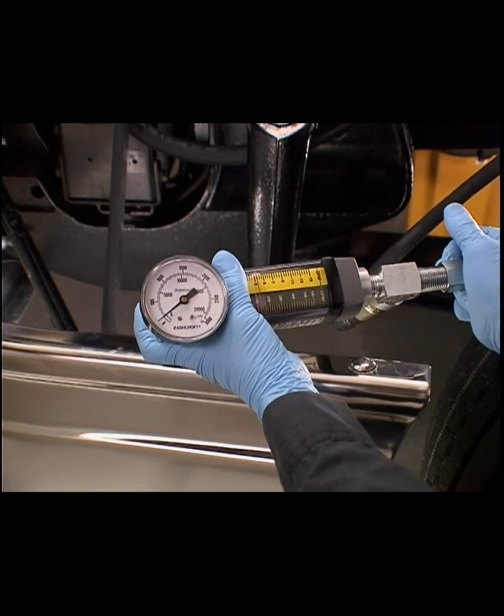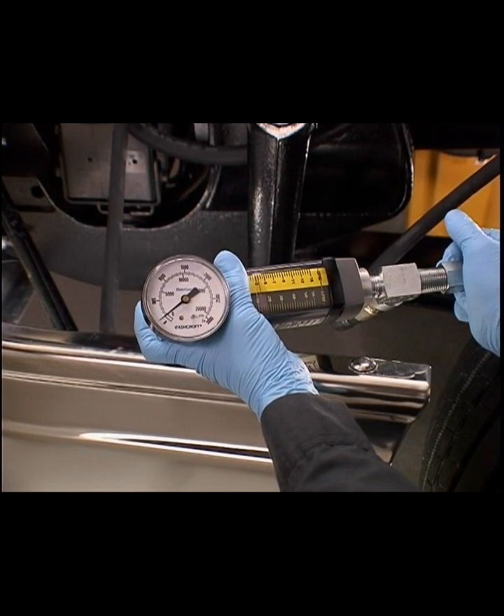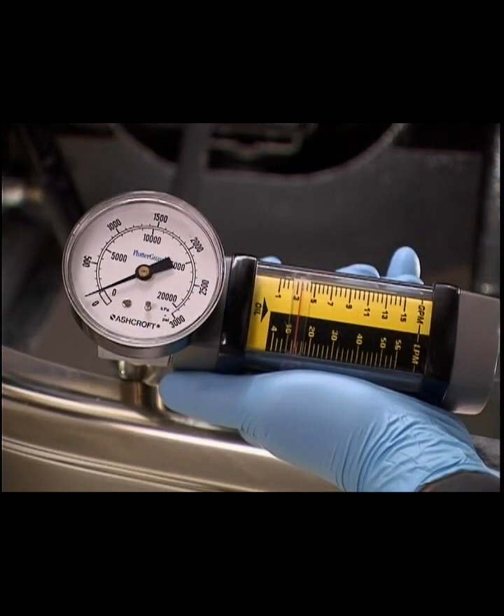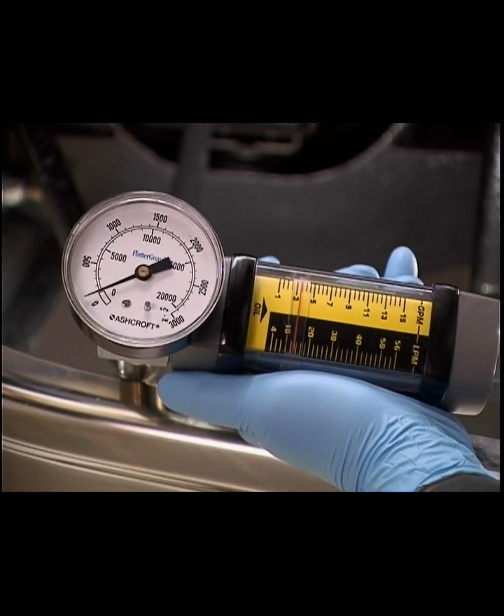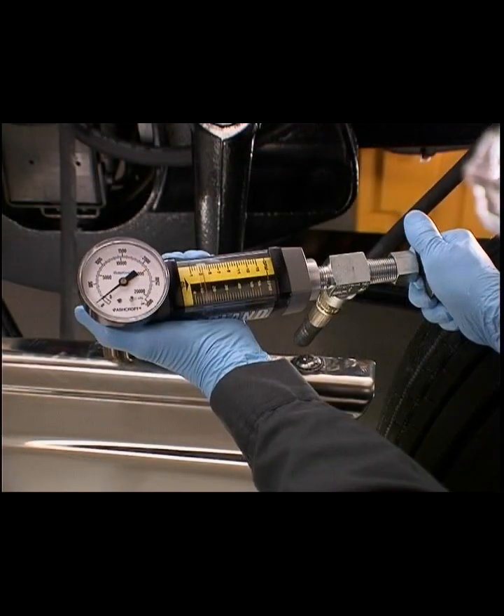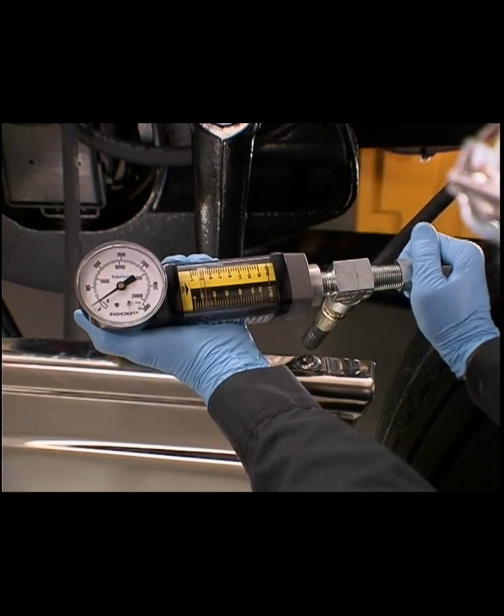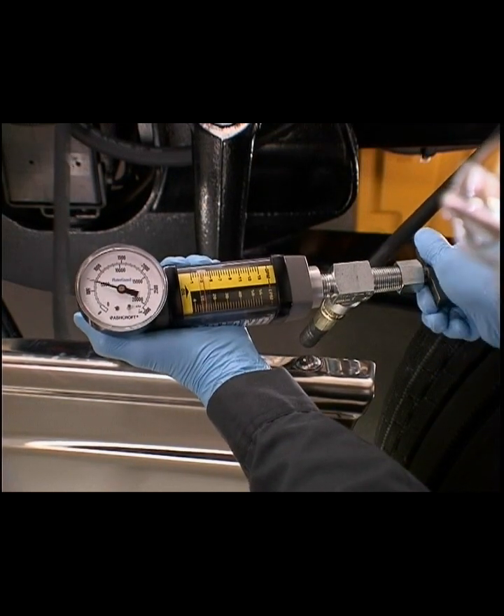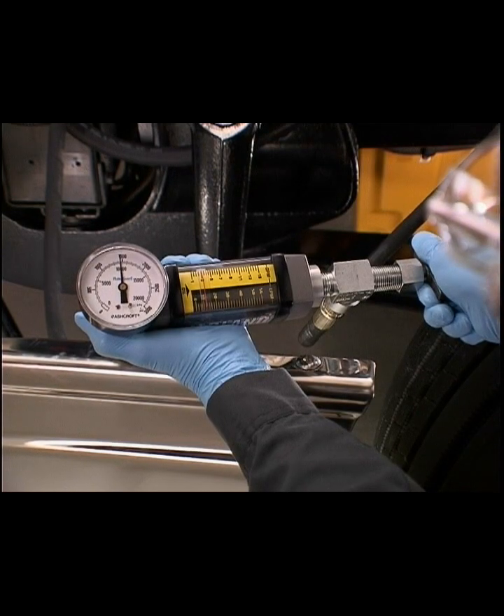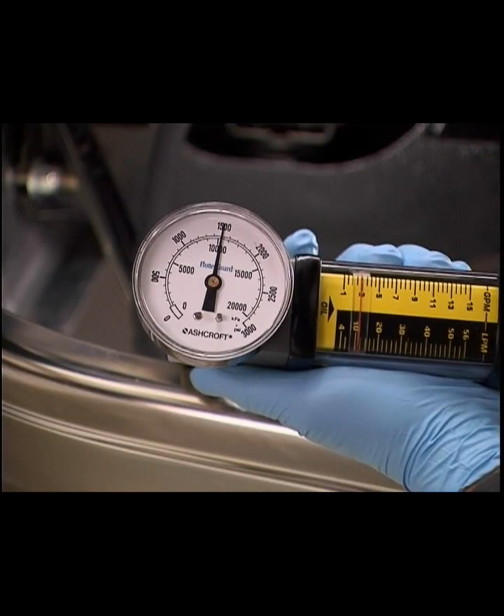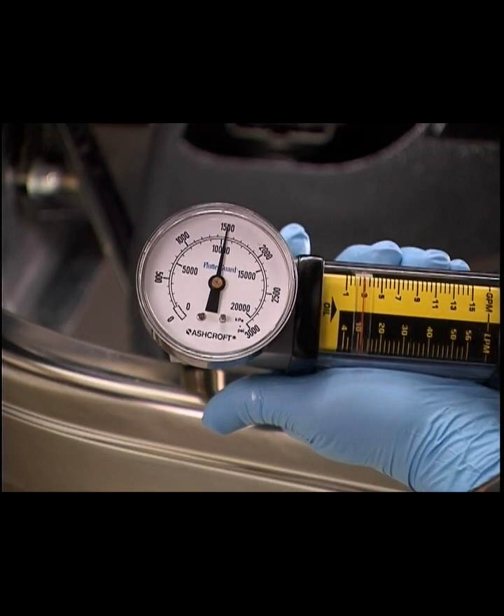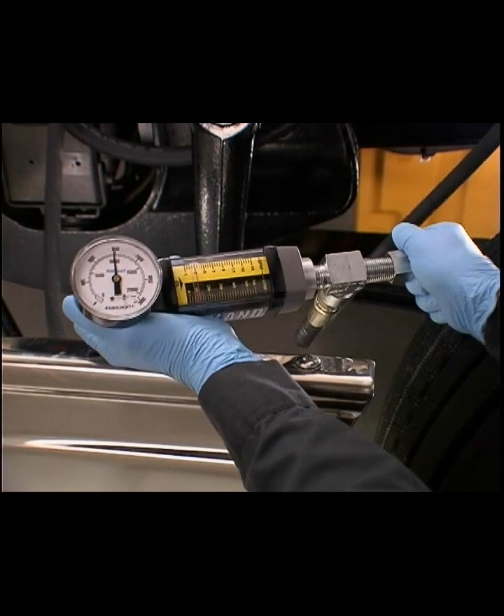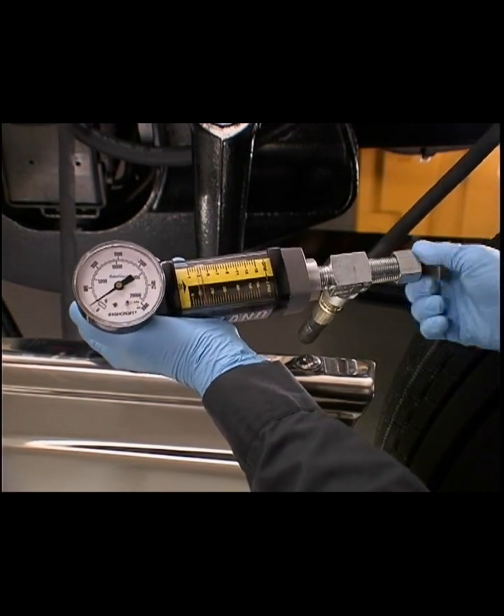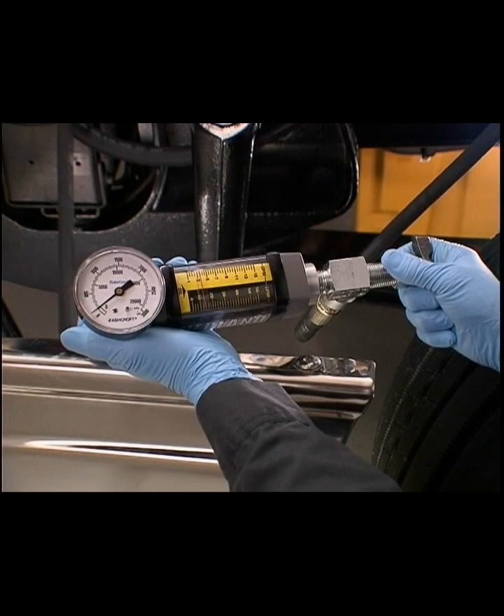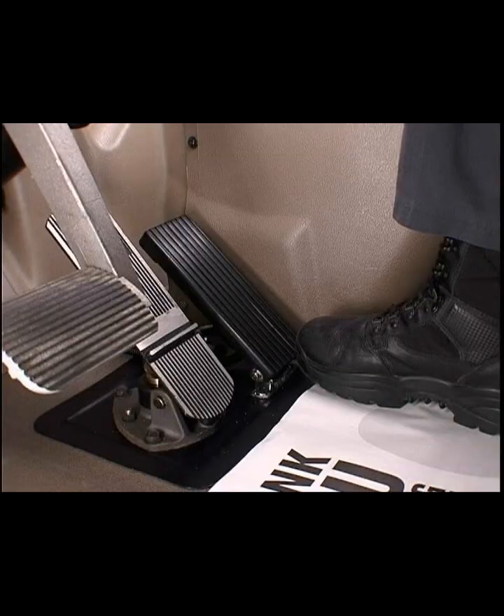Now measure and record the flow at idle, back pressure only. This is read in gallons per minute with the valve all the way open. Then measure and record the flow at idle with 1500 psi load applied by closing the valve to read 1500 on the gauge. Open the valve and with the assistance of a second technician to work the engine throttle, measure and record maximum engine RPM.